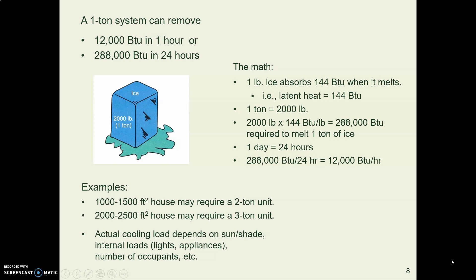Air conditioners and heat pumps use a refrigeration cycle. There's liquid refrigerant, some kind of Freon, flowing through tubes in the system. Freon is a brand name made by DuPont. It's all about latent heat: if the liquid refrigerant changes to gas, like boiling, it absorbs heat, and so it can absorb heat out of your room.